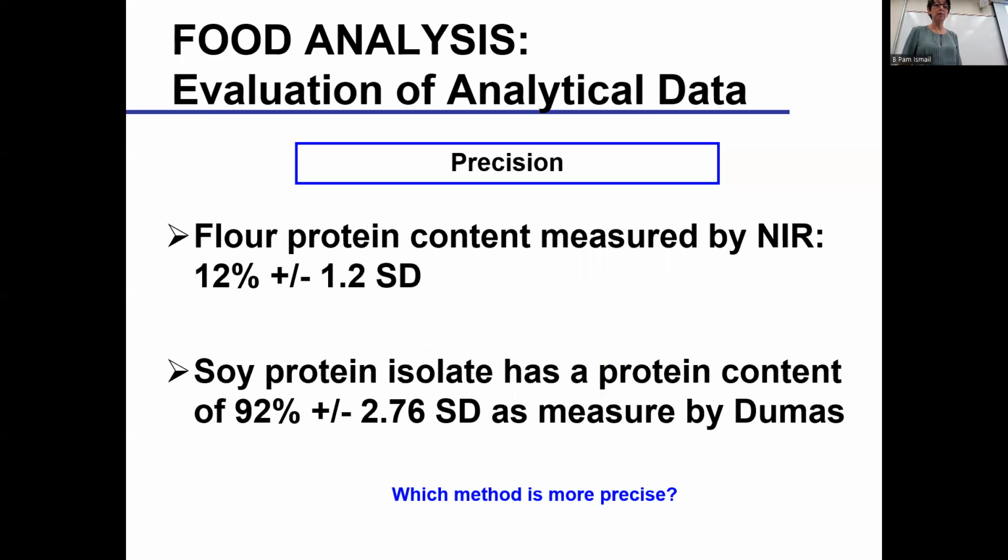I'm going to illustrate. Take the near infrared instrument, NIR; we learn about it later under the spectroscopy section of the class. In NIR, you can do quick measurements of composition. You calibrate the unit using primary methods of analysis, and then you can put your powdered sample directly in the instrument and get a measurement within seconds.